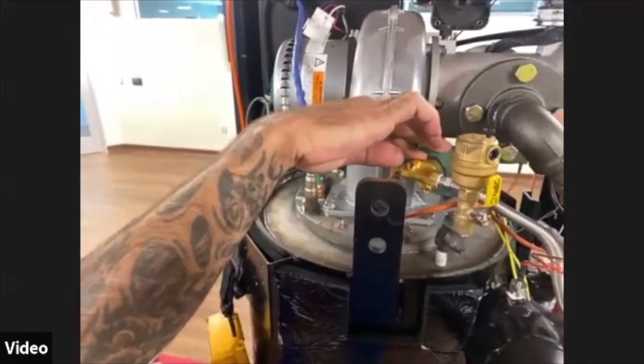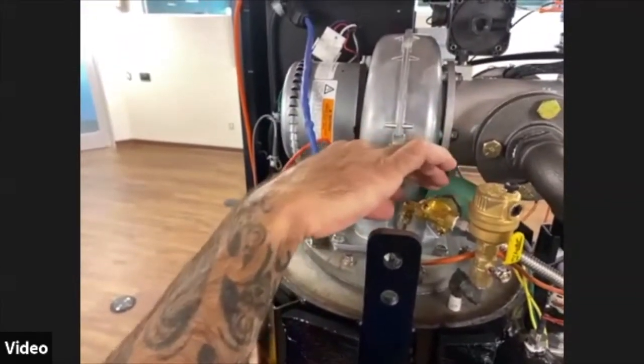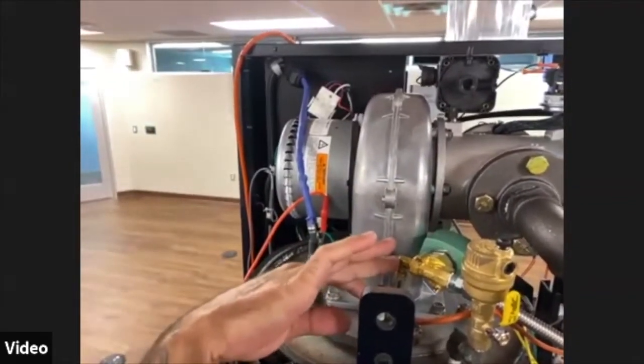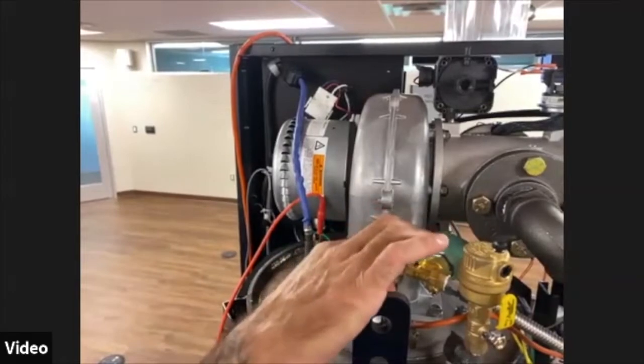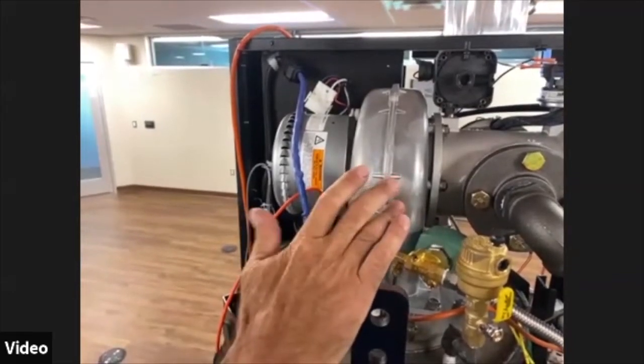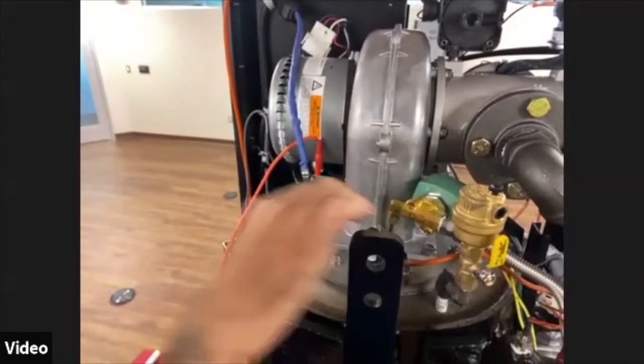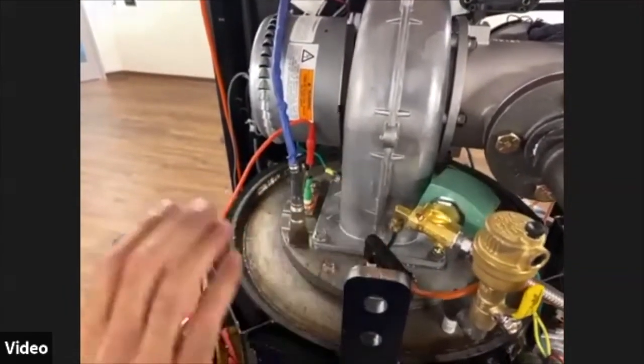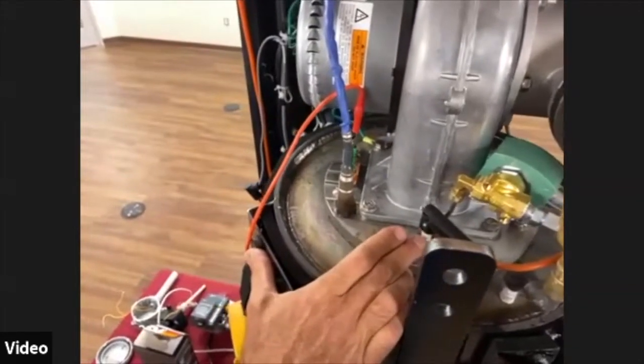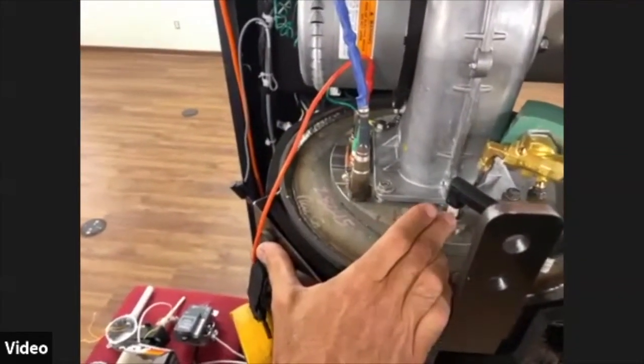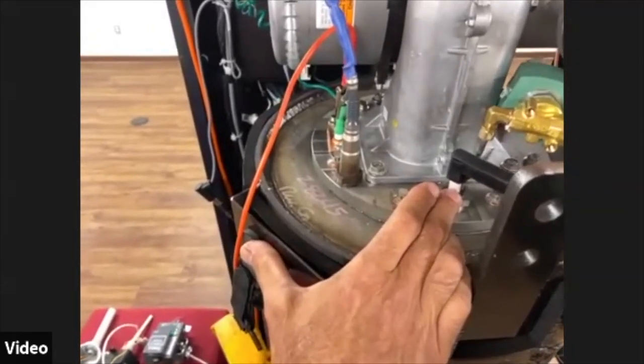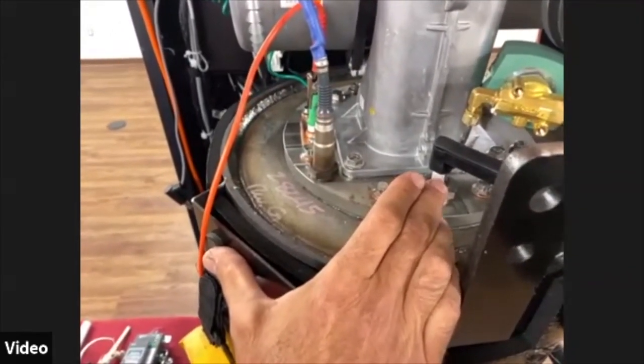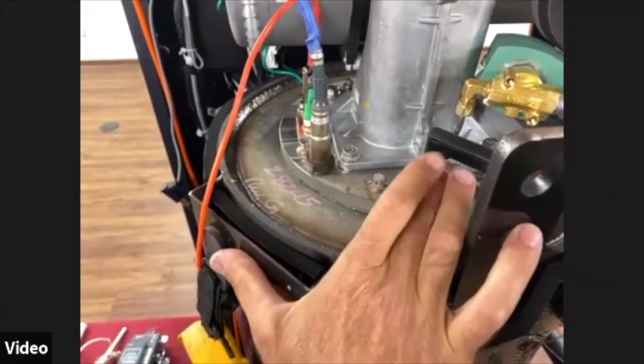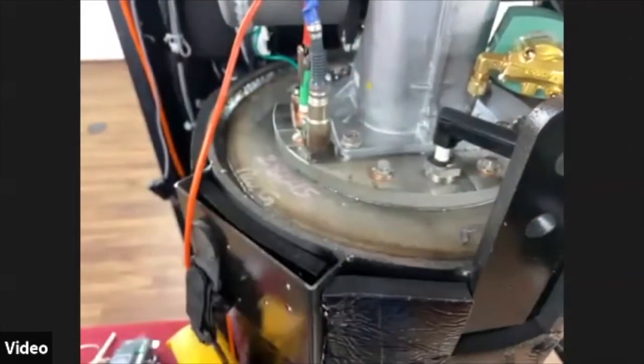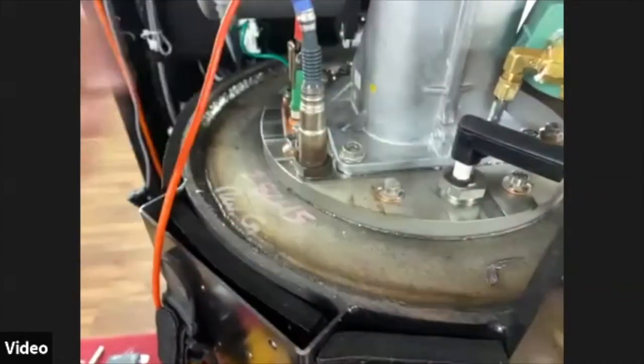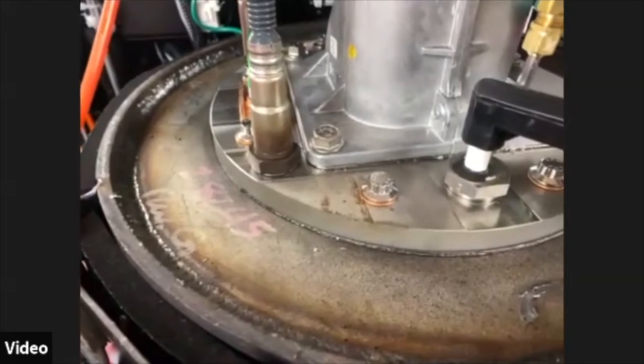This is our pilot solenoid. Our pilot solenoid is connected to our fan jet style igniter. So basically, the pilot solenoid opens, sends a flame down, we spark, we ignite that pilot, and then we light the main burner off of there. One of the things important to remember with the fan jet igniter, if you replace this igniter with one off of your truck or from the factory, I would recommend that you put a mark on this somewhere and mark it to the top plate of the heat exchanger or your burner plate. Make it easier for you to reinstall it.